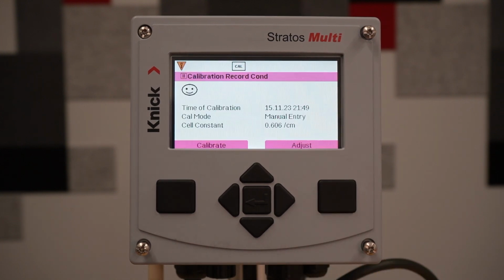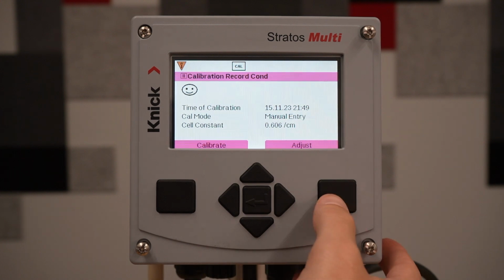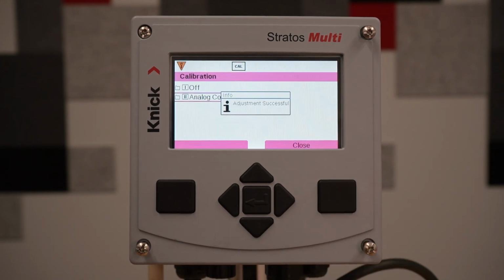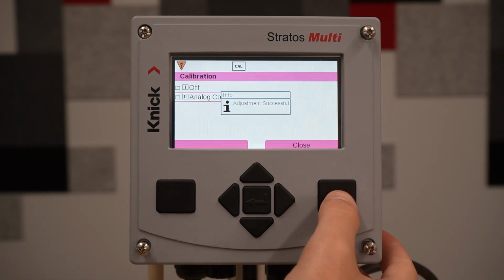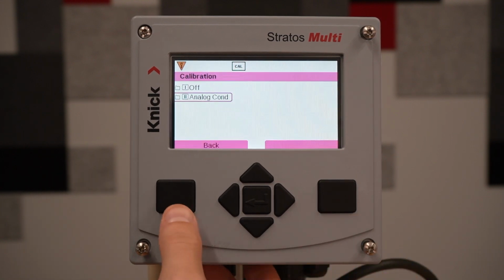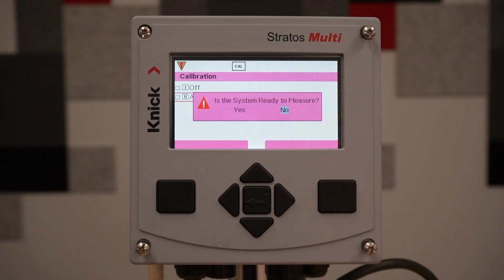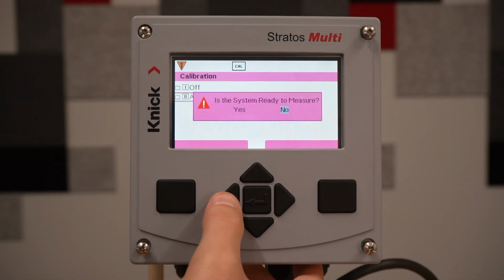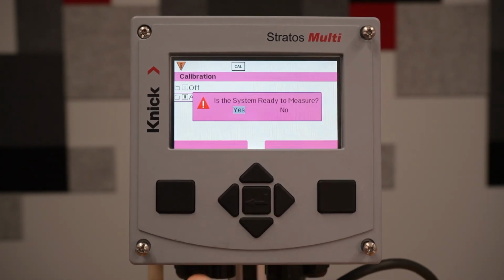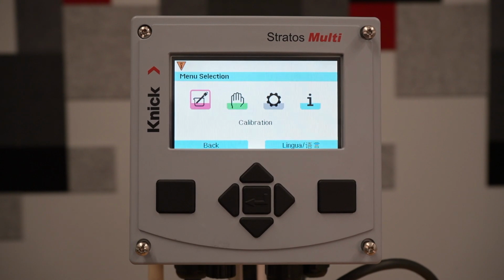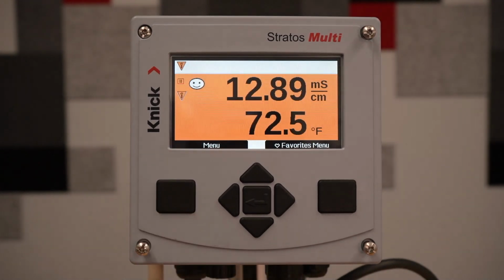It will go into my cell constant, and then I will hit Adjust. The adjustment or calibration was successful. I can close out of this. Now when I hit back, it will ask me if the system is ready to measure. I will click Yes. We can then go back to the main screen. The hold mode will be released, and the sensor will enter into measurement mode.